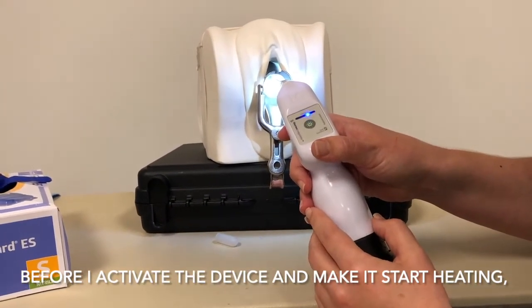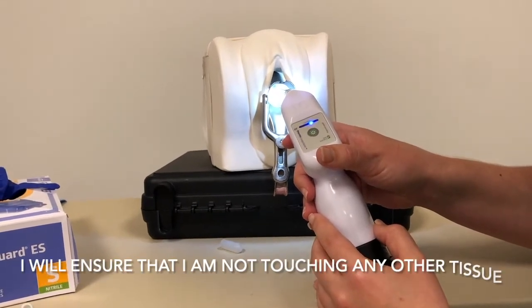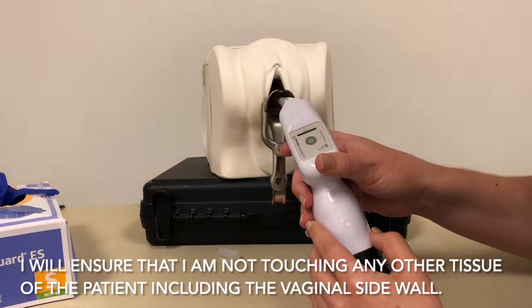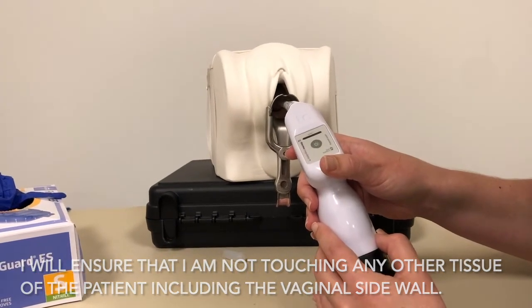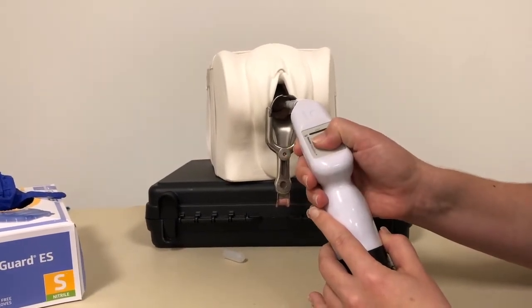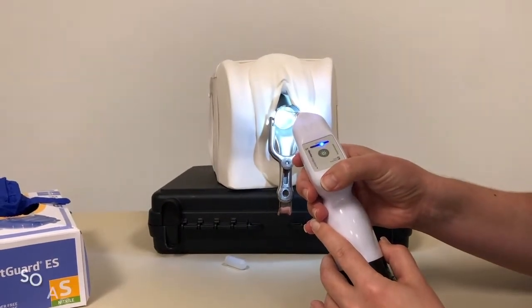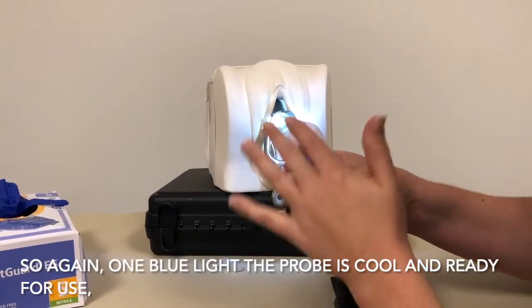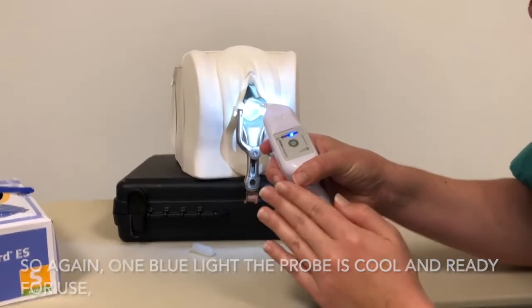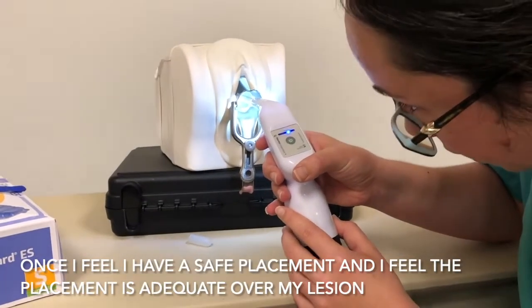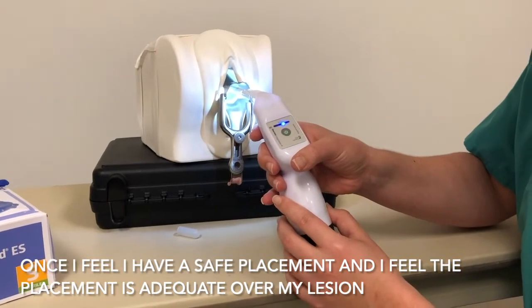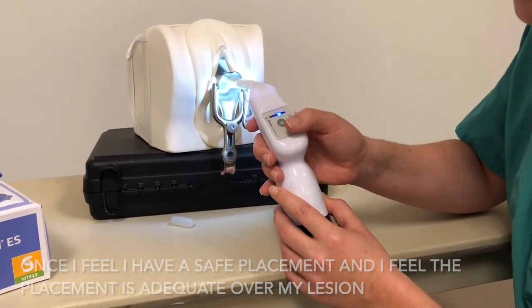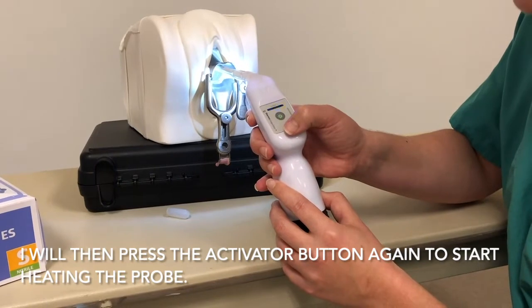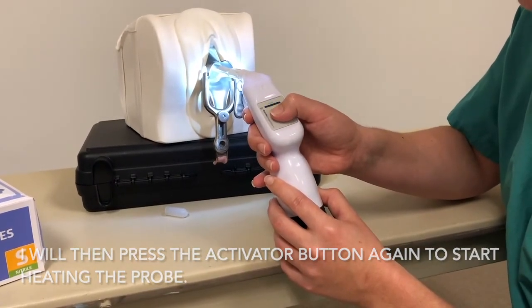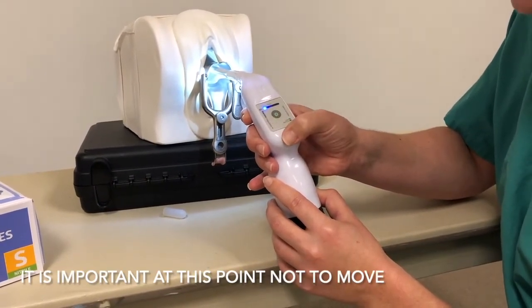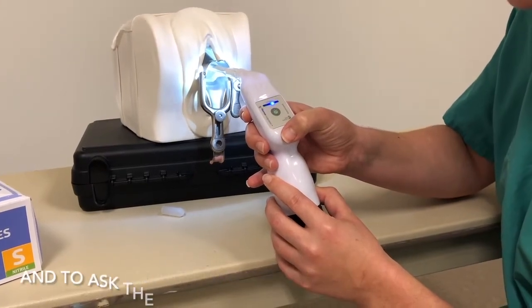Before I activate the device and make it start heating, I will ensure that I am not touching any other tissue of the patient, including the vaginal sidewall. So again, one blue light, the probe is cool and ready for use. Once I feel like I have a safe and adequate placement over my lesion, I will then press the activator button again to start heating the probe. It is important at this point not to move and to ask the patient to remain still.